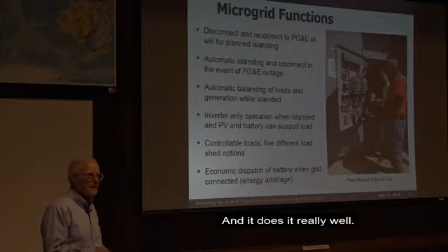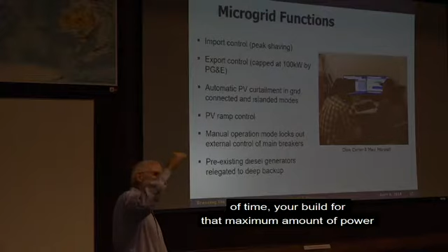One of the things this system does as well: when you pay your electric bill and you're a big customer like BLR, a large fraction of your bill is not just the energy you use, but the power you drew from the grid. So if you draw a certain amount of power for a short period of time, you're billed for that maximum amount of power you drew that month. So it behooves you to shave the peak and keep it as low as possible within reason so you can run all your loads. Again, the optimizer does that, sets a level, doesn't allow the peak to get too high, and therefore decreases the bill. We'll show you the data.